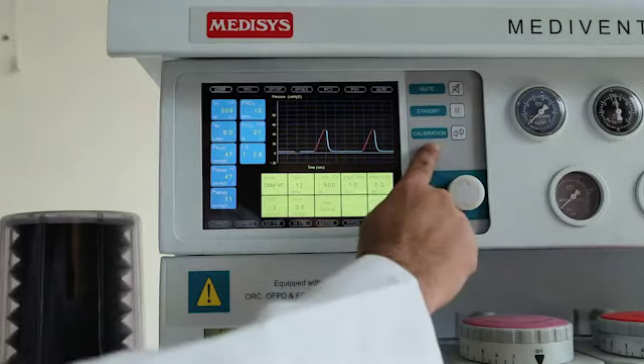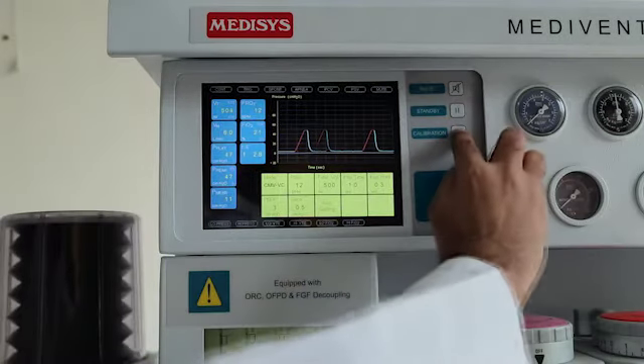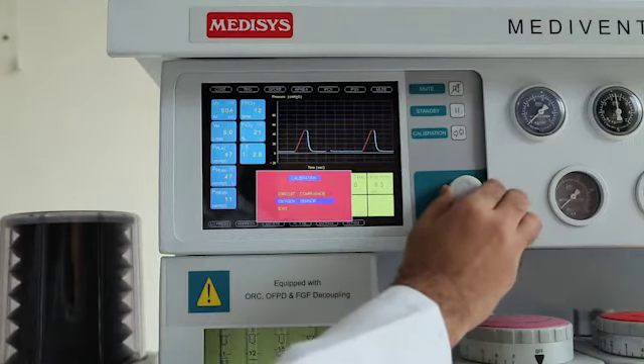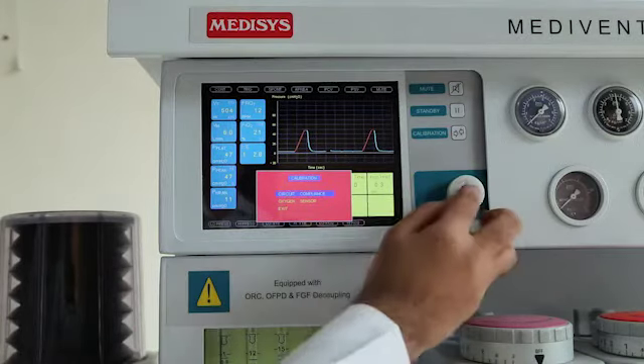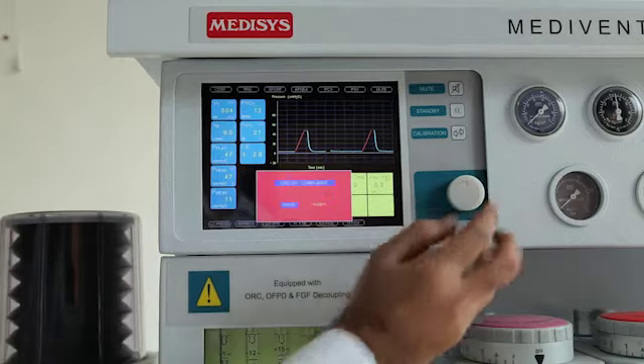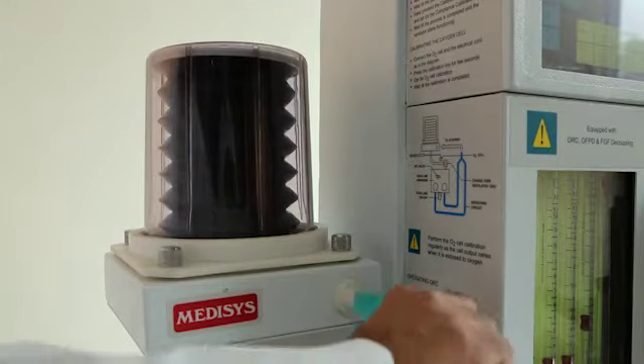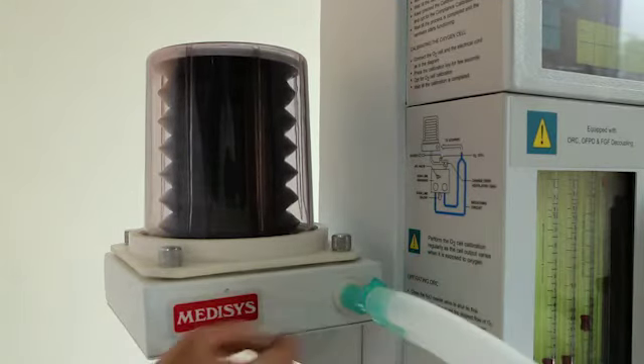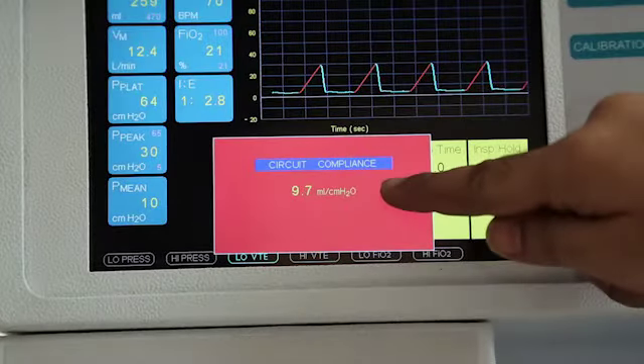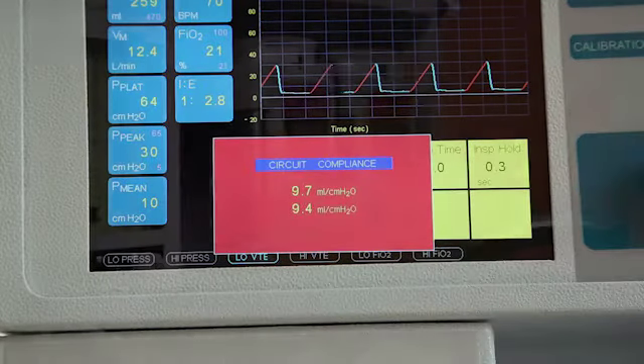There is a compliance calibration. This is also a very unique thing. You know that every part of the machine, the breathing circuits and all, has its own compliance, and it may change with the flow and with the size of the tubing. This machine automatically calibrates the flow according to the compliance.